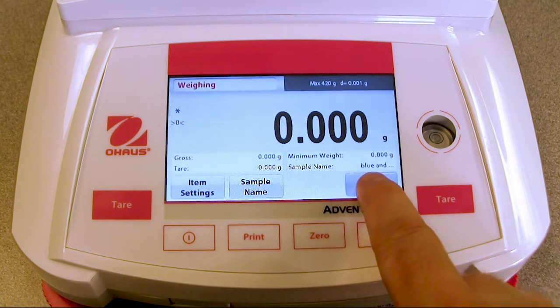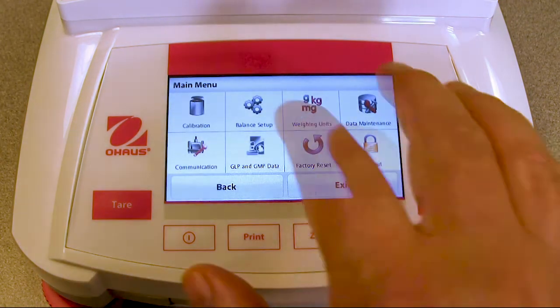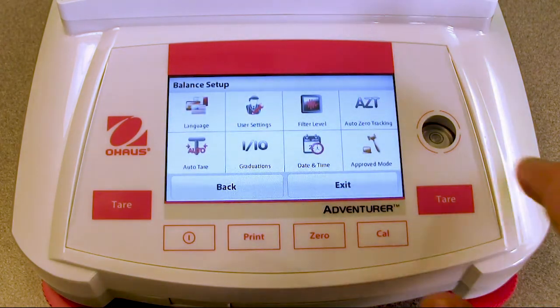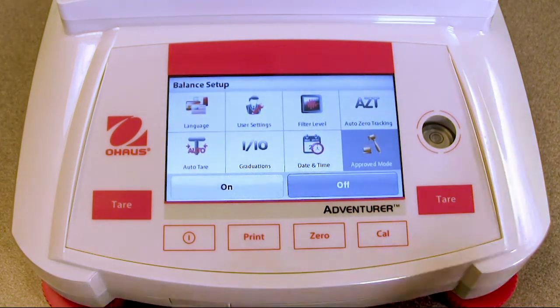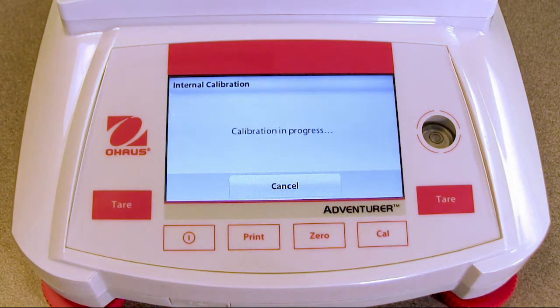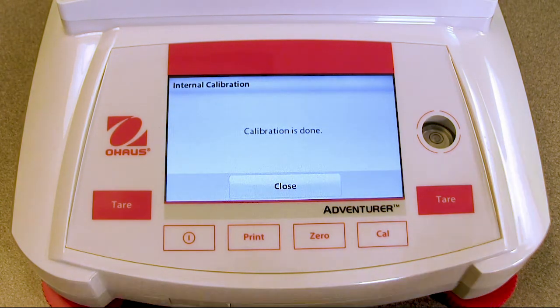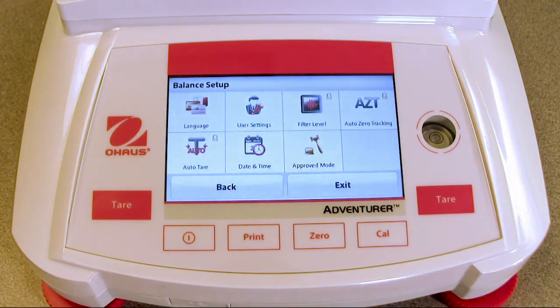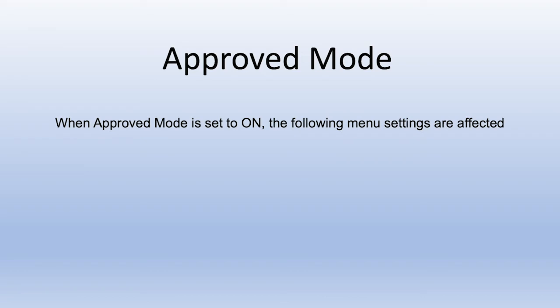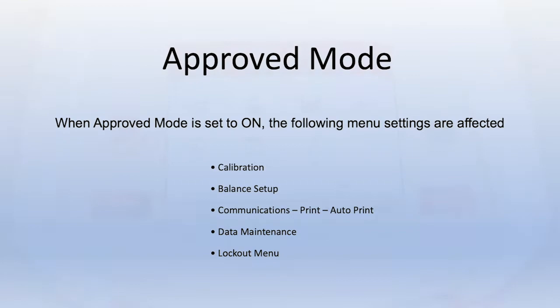The approved mode is used to set the legal for trade status. When set to off, the balance is in standard operation. When on, the operation complies with legal metrology regulations. When the approved mode is set to on, the menu settings are affected as follows: the calibration menu, the balance setup menu, the communication menu, print and auto print, data maintenance, and lockout menu.